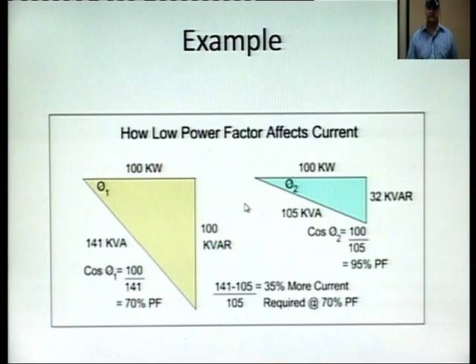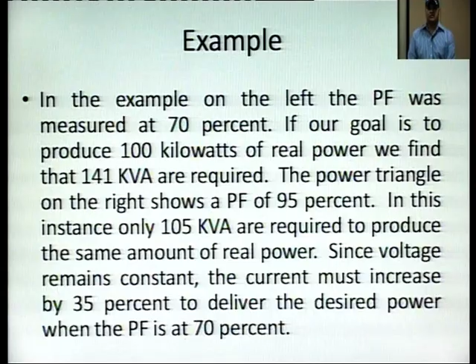It is given in the theory that in the example on the left, the power factor was measured at 70%, and if our goal is to produce 100 kilowatts of real power, we find that 141 kVA are required. The power triangle on the right shows a power factor of 95%. In this instance, only 105 kVA are required to produce the same real power. Since the voltage remains constant, the current must increase by 35% to deliver the desired power when the power factor is 70%. So if the power factor is improved from 0.7 to 0.95, we require 35% less current. And 35% less current means we can use smaller wires and smaller equipment for the same power.